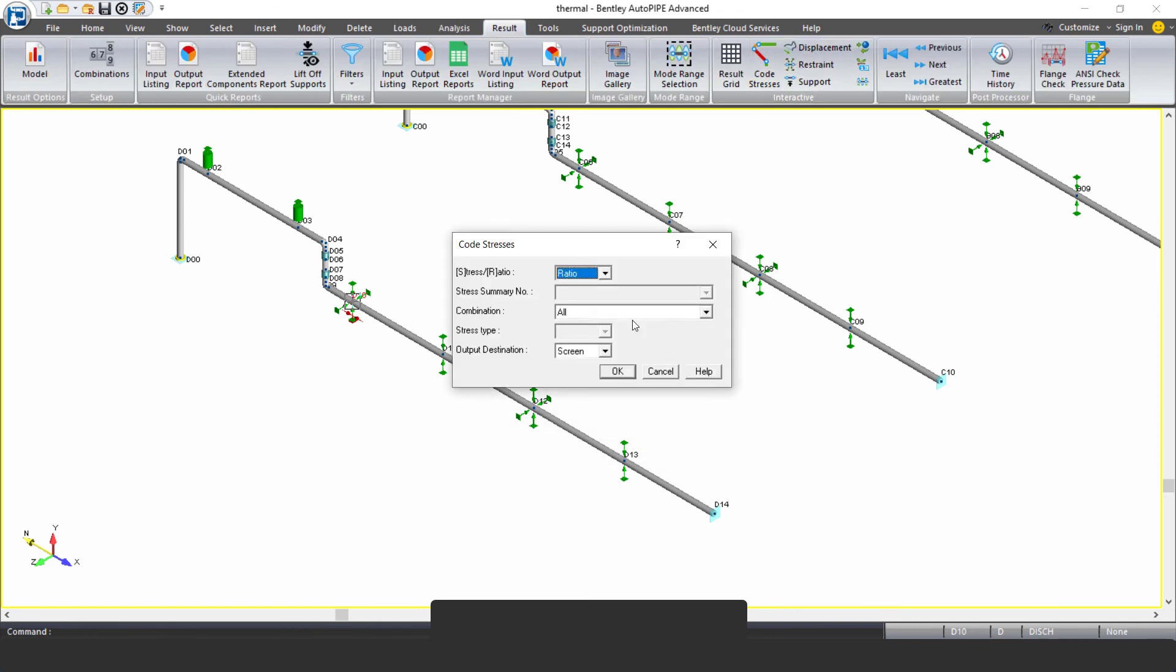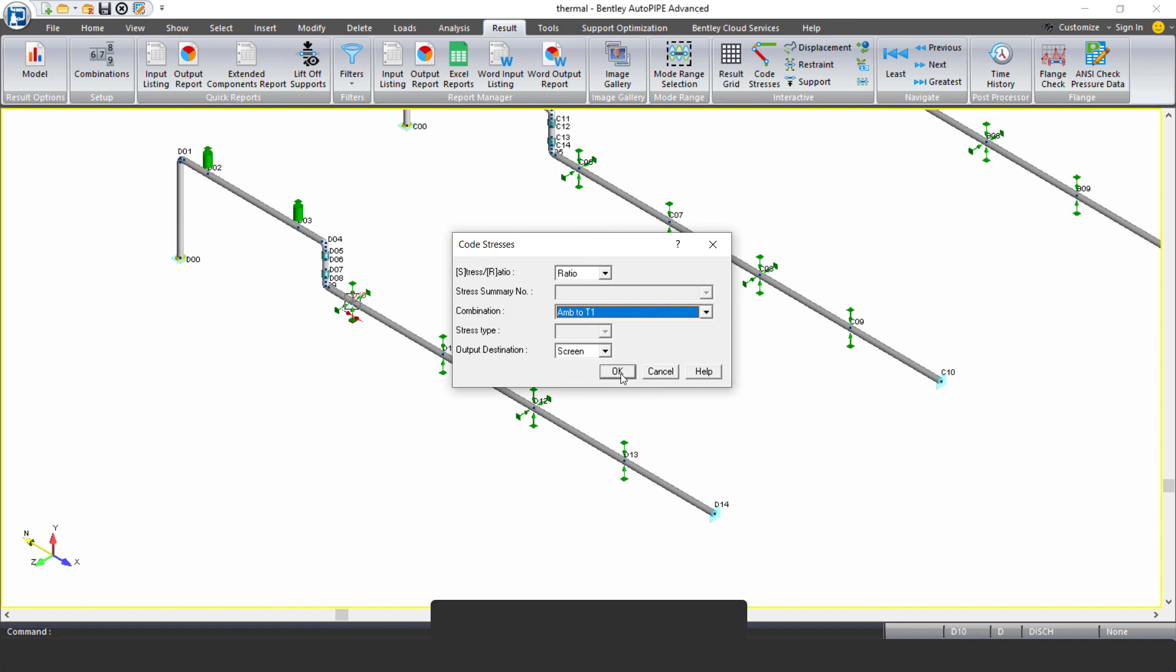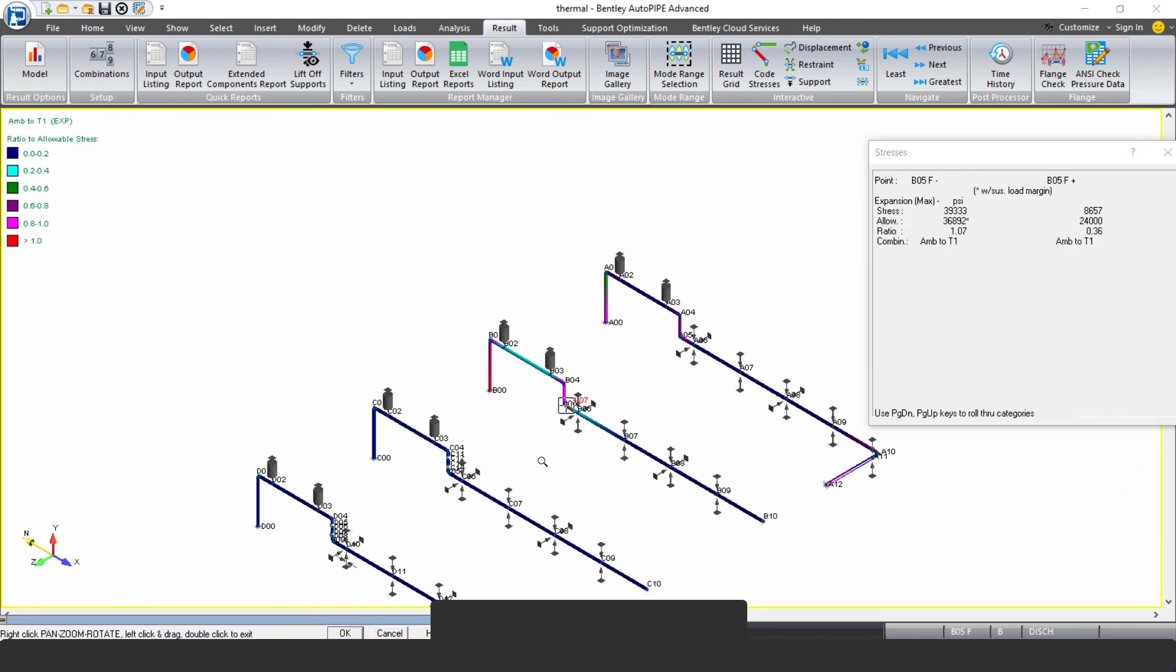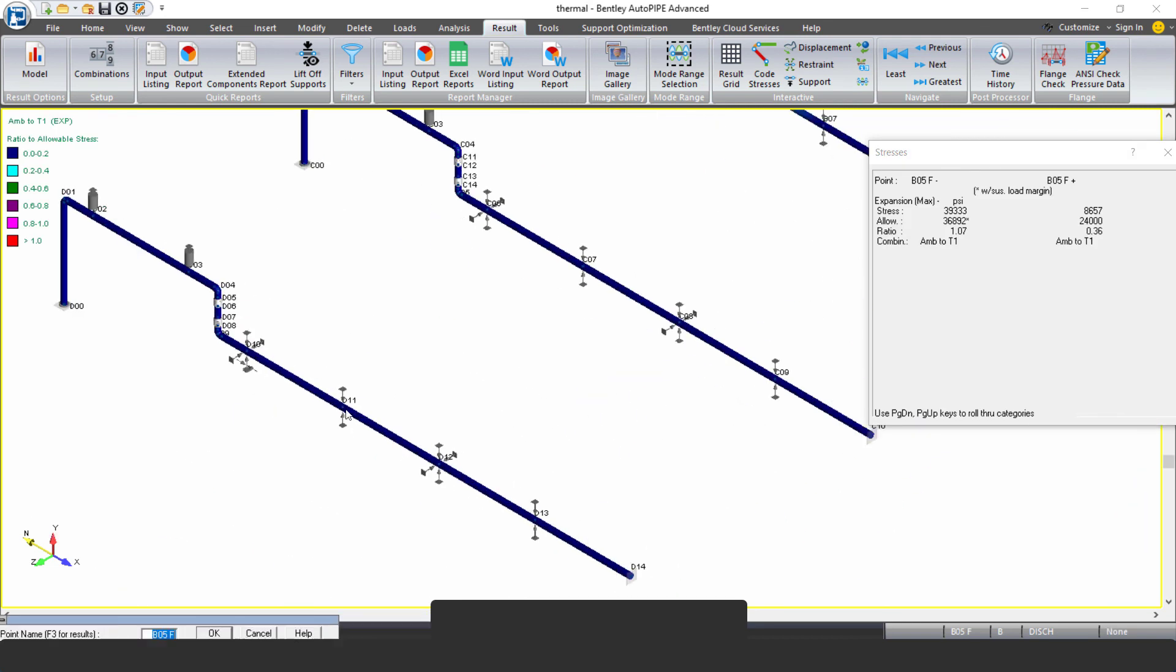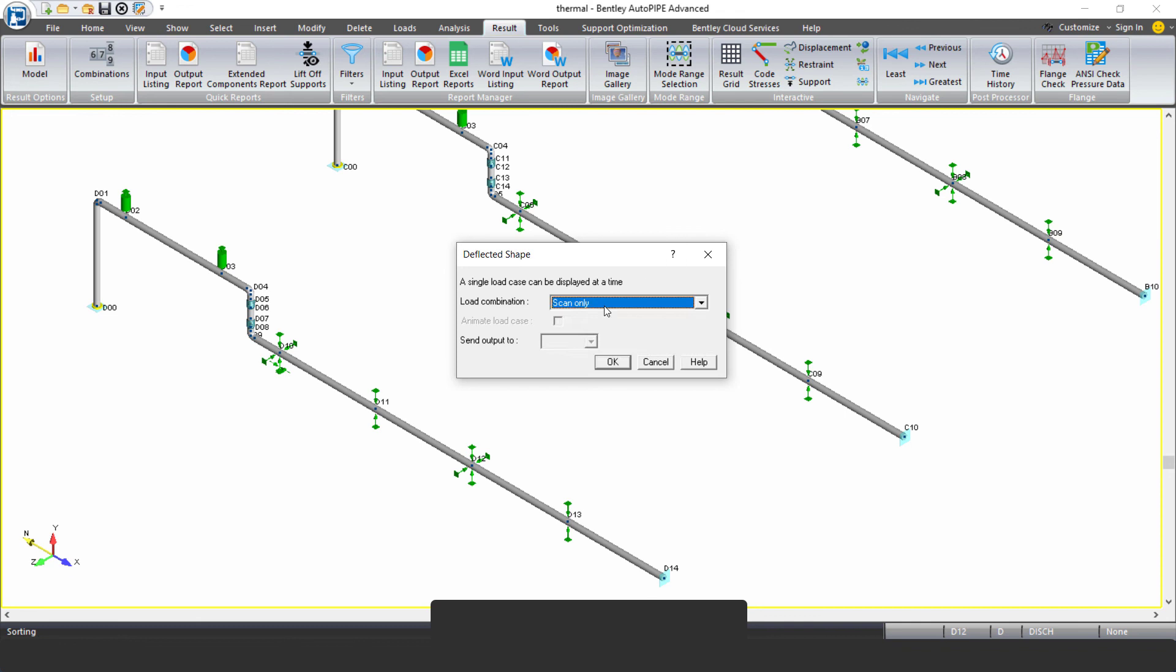again, I'll look at my code stresses. Now that's really important because I'm trying to see when I put this line stop in, am I causing high thermal stresses here because this pipe is trying to grow and I'm stopping it? And no, that didn't really cause many issues here throughout this section of pipe.